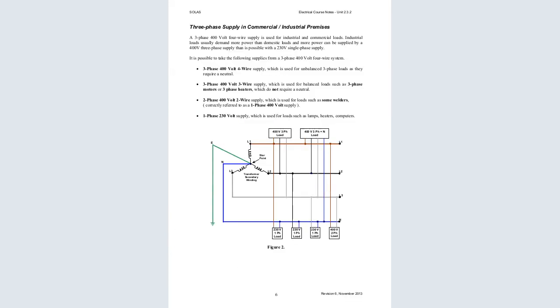You can see one of the red phases, the line 2 is here and line 3 is here, but it does not have a neutral. And we also have another load that now has a neutral. We have one there, we have another one there, and we have another one there, and the neutral is there. So all the balance load that we talked about here, yes, SOLAD.